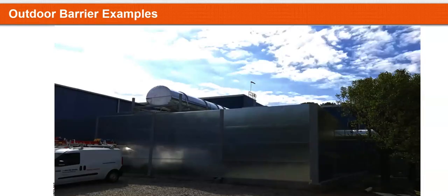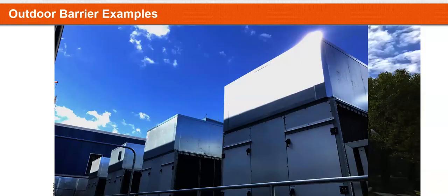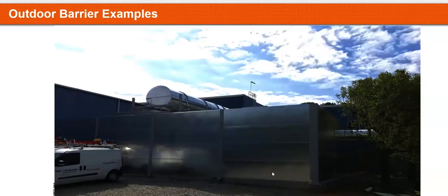Another example is this bakery in Atlanta. We also sized that barrier wall, including absorptive panels at the back wall so that sound didn't reflect over, including some localized barriers or discharge plenum barriers for the condensing units at the top, to make sure that the residents within 50 feet, because they had to put all the equipment at ground level facing homes, weren't complaining. So all that was done after the fact, when they had to put the equipment. However, the fact that we had access and they could pour a new concrete pad made it a smooth process.